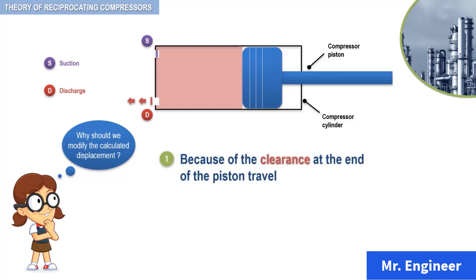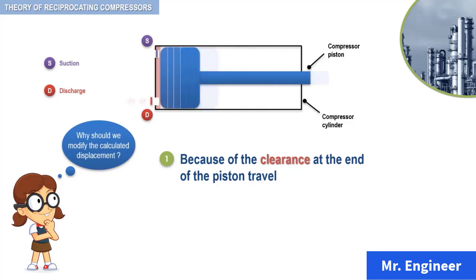Earlier in this section, when the compression cycle was described, a portion of the pressure volume indicator diagram was referred to as the expansion portion of the cycle. The gas trapped in the clearance area expands and partially refills the cylinder, taking away some of the capacity.